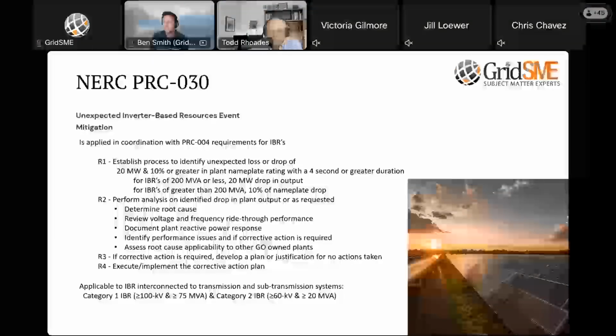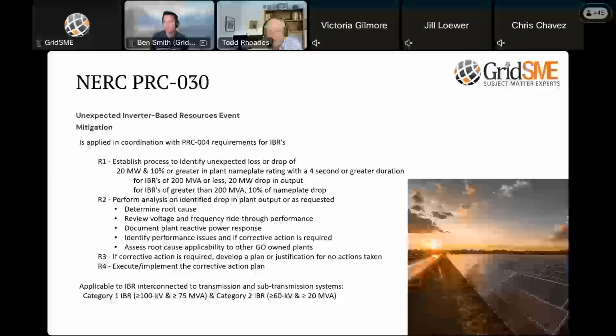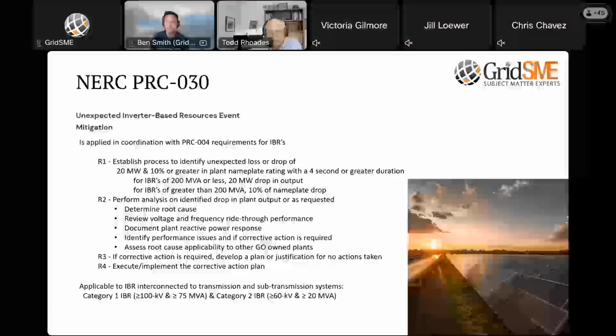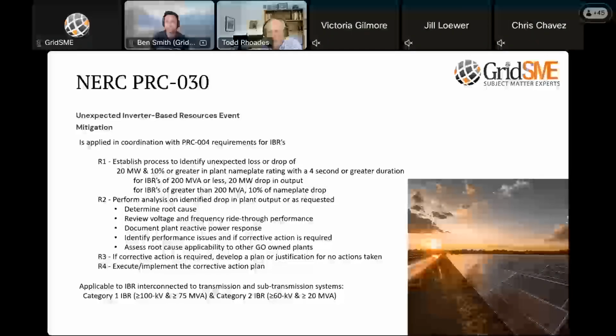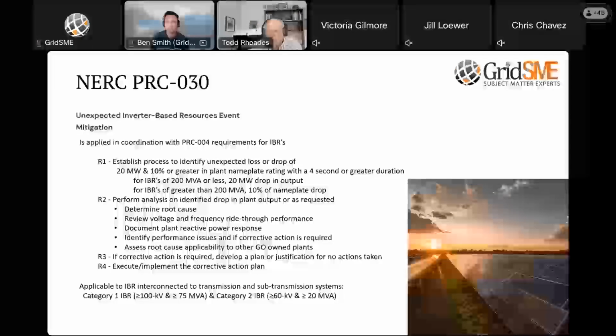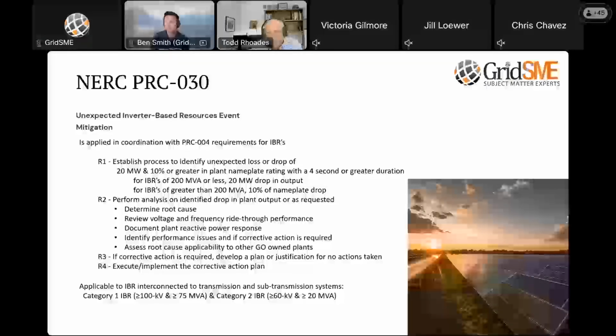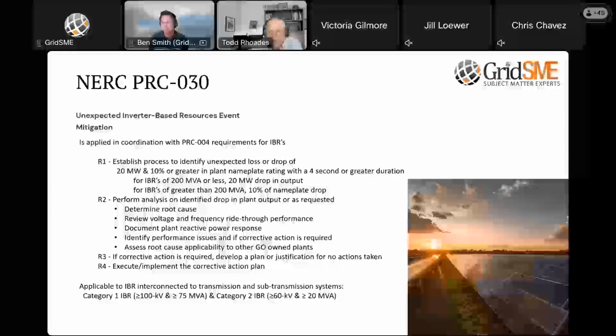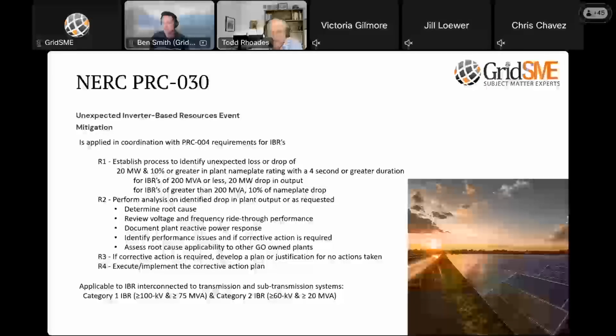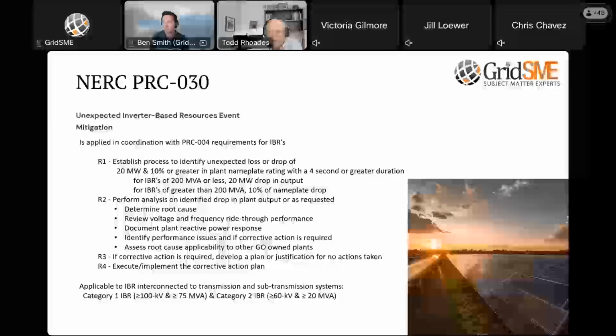So again, there are four requirements. The first requirement is a process for identifying when a variation in the output of the plant has occurred, and it's defined as being of at least 20 megawatts and 20% or 10% or greater of the nameplate rating of the plant with a duration of at least 4 seconds. So what does that mean? If your plant is 200 MVA or less, then the 20 megawatt drop in output becomes your driving characteristic. If you have greater than a 200 MVA plant, then your 10% of nameplate becomes your consideration.